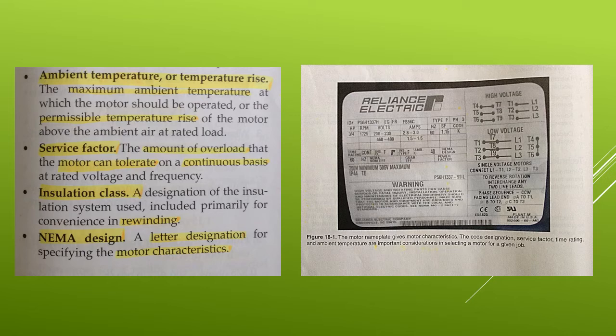Frame number. Motors of a given horsepower rating are built in a certain size of frame or housing. For standardization, NEMA has assigned a frame number to the frame size for each integral horsepower motor. This ensures that the shaft heights and dimensions are consistent for motors that are assigned a specific frame number.